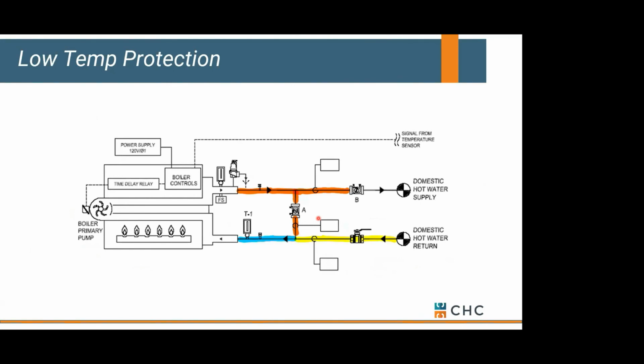Well, we're going to add something we might call a bypass in the field, and then some manual ball valves, which we call circuit setters. And that 90 to 100 degrees that's coming out of our storage tank simply rolls into our heater. We heat it up. There's a pump on the back here. We send hot water back to the storage tank, but we don't let all of it go to the storage tank. We start to throttle this valve, circuit setter B, down.